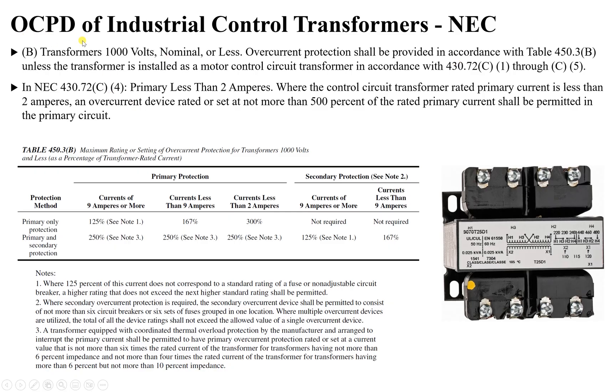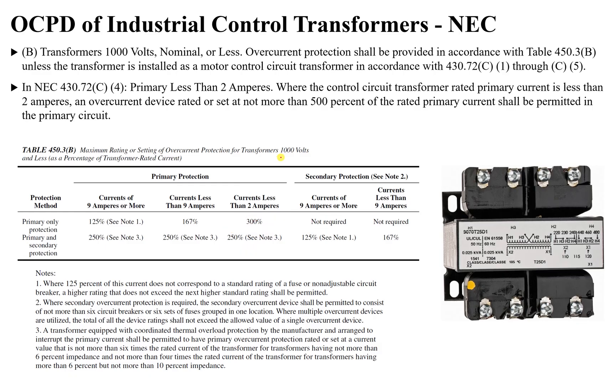NEC 430.72(C)(4) addresses sizing the overcurrent device. The table shows values of 300% and 250% for primary currents, but it says: where the control circuit rated primary current is less than 2 amperes, use an overcurrent device rated or set at not more than 500% of the primary current — instead of the standard 300%. This exception exists because these smaller transformers have higher inrush currents. Understanding this NEC rule is essential for correctly sizing overcurrent protection for industrial control transformers.